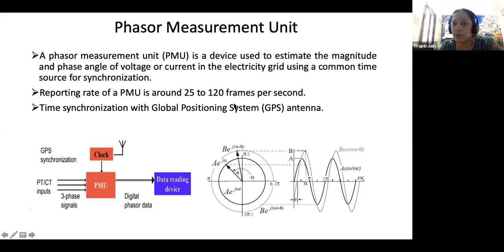So here this shows you a substation. This substation has these two generators. We are placing a PMU here, and we are placing a PMU here also, and when we are measuring, these two PMUs will be time synchronized through GPS. So you are measuring the voltage phasors at this bus, the voltage phasors at this bus, and the current phasors in this line also. This is a small system just to show how it will measure and then transmit. Because they are synchronized with the GPS system, at the same time instant they are measuring the voltage phasors here and the voltage phasors here.